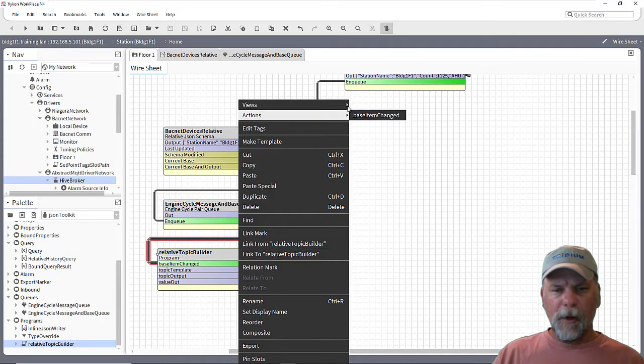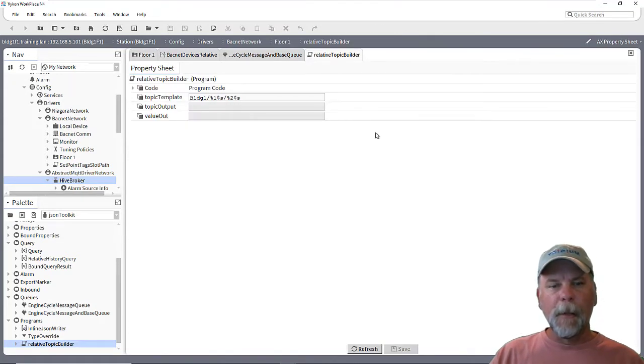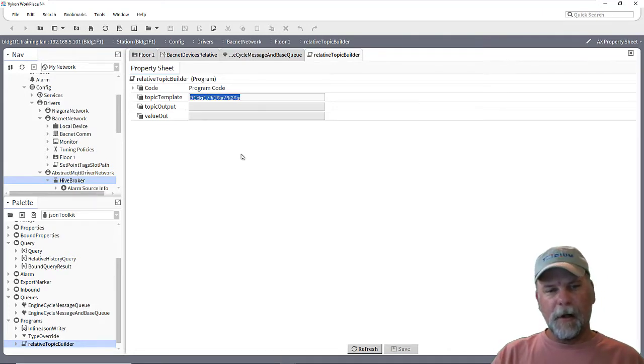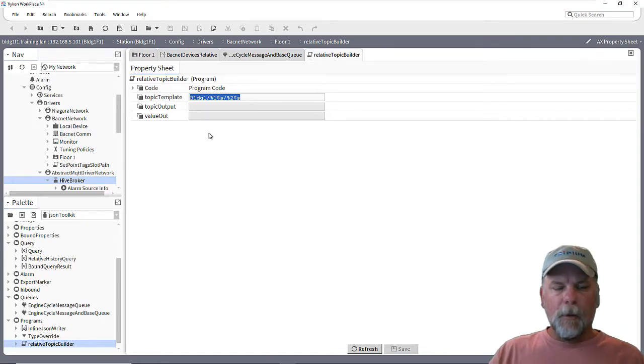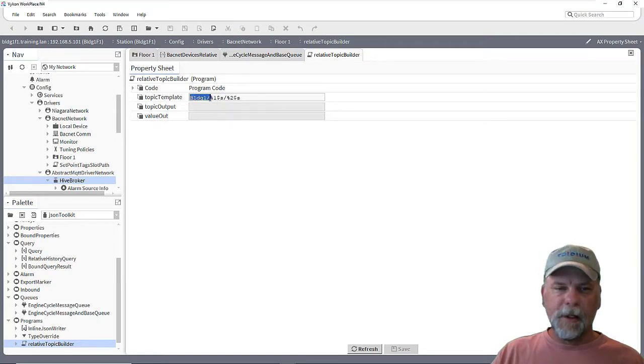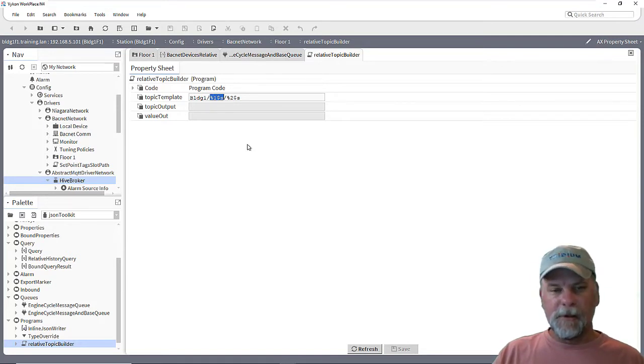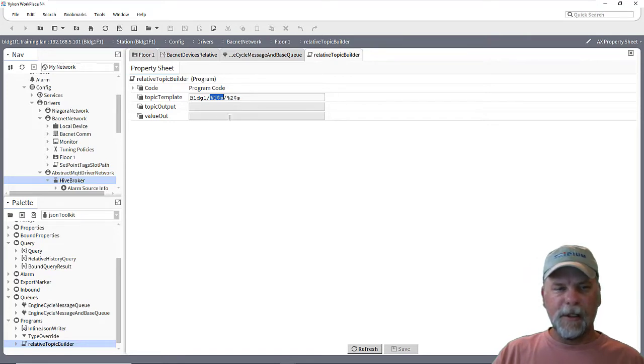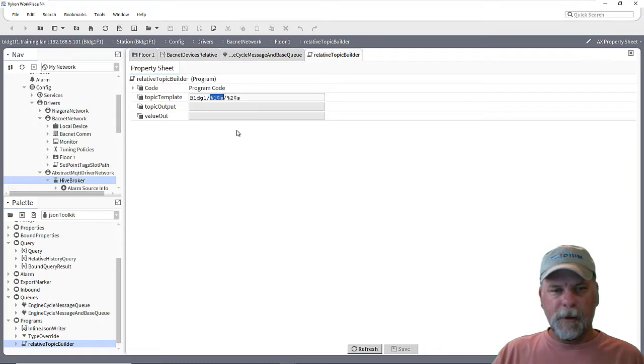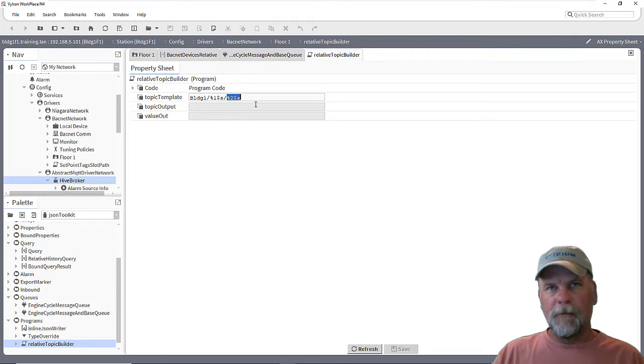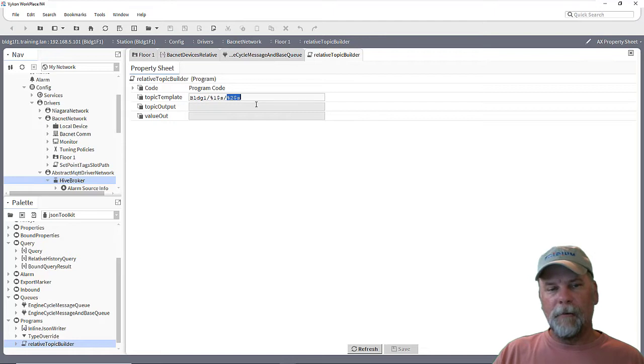And when I look at the property sheet of the program object, what you'll see is there's a topic template here, which is a string property. And this is where I can define what the topic is going to look like that gets used. And what I've done is building one here and then a forward slash. And then in the string, there's essentially a string variable here that I want to substitute when the program object runs and that'll plug in what the floor is. And in this case, it's actually going to use the display name of the floor. So instead of floor with no space one, it'll be floor space one. And then a forward slash and then another string variable essentially that'll resolve the display name of the air handler device being processed.